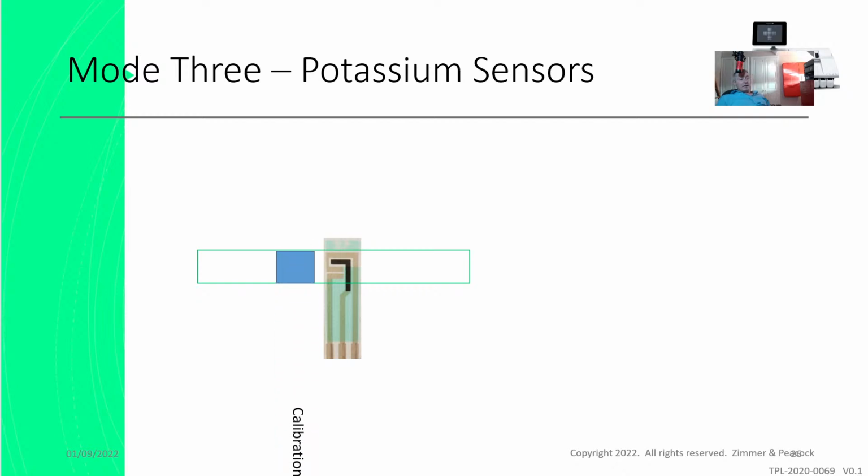They have a calibration solution that flows over the top of the sensor, and then behind it they have the real sample. They almost do a calibration and then read the sample. Somebody came to me today and said, I want to make potassium sensors, and I want to make a benchtop instrument, and I've got pumps and calibration solutions. That, from our perspective, is really quite straightforward. From the perspective of where you want to read potassium in blood capillary, that is a lot tougher.